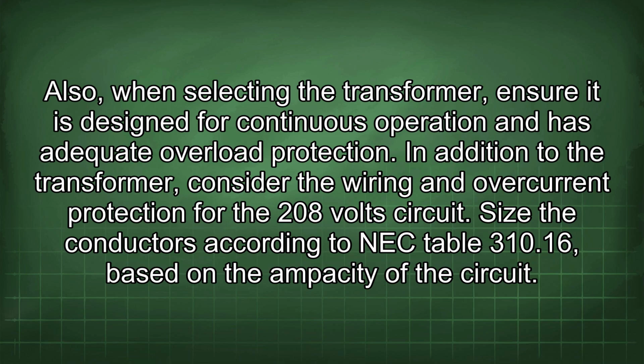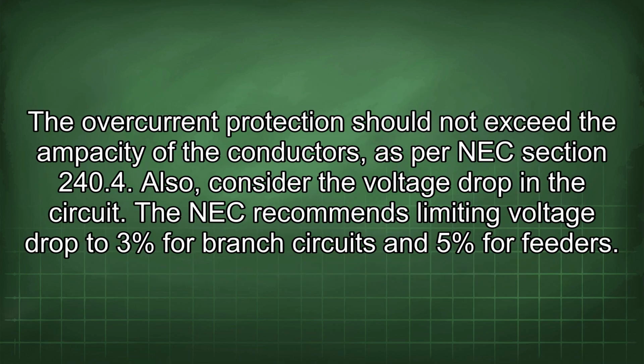In addition to the transformer, consider the wiring and overcurrent protection for the 208 volt circuit. Size the conductors according to NEC Table 310.16 based on the ampacity of the circuit. The overcurrent protection should not exceed the ampacity of the conductors as per NEC section 240.4.